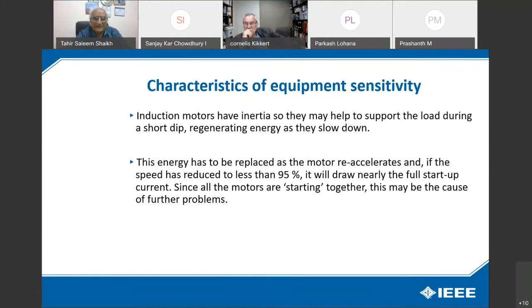Induction motors have inertia, so they may help to support the load during a short dip, regenerating energy as they slow down. They become a generator. This energy has to be replaced as the motor re-accelerates, and if the speed is reduced to less than 95%, it will draw nearly the full startup current. Since all the motors are starting together, this may be the cause of further problems.